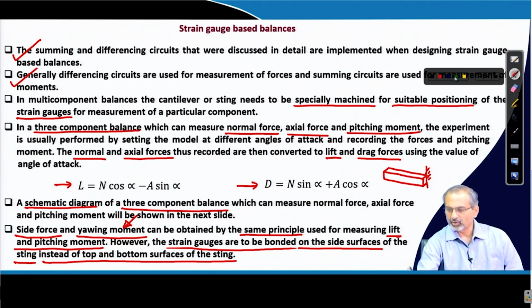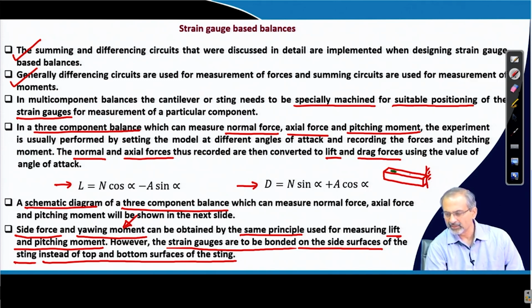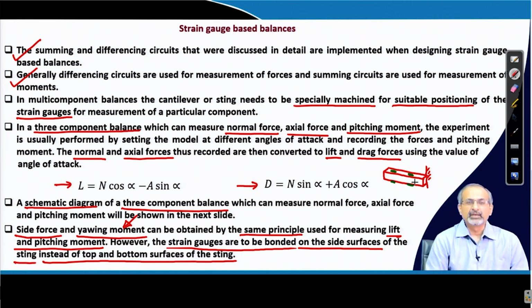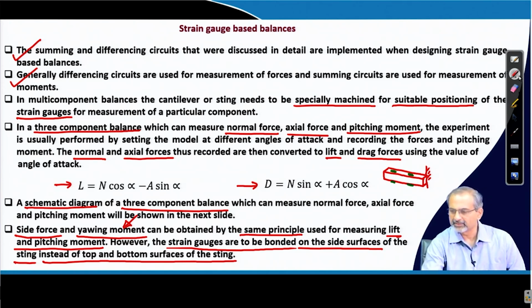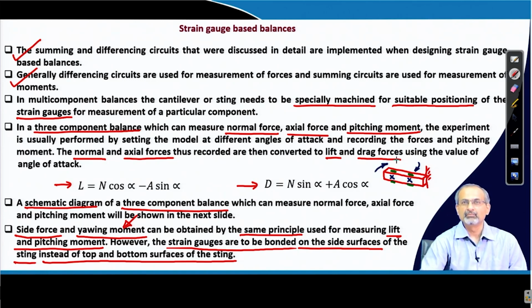We were talking about placing load cells on the top and bottom surfaces for obtaining lift and pitching moment. However, for side force and yawing moment, you would use the side surface and the opposite one not visible in this view, since that is the direction in which the sting balance deforms under side force and yawing moment. We are essentially changing the plane in which the deformation or strain occurs, so the strain gauges must be mounted on the side surfaces instead of the top and bottom.